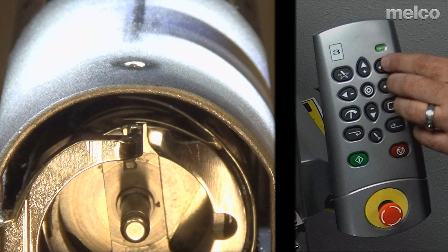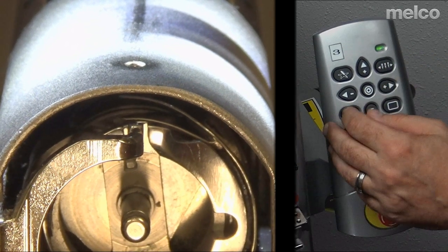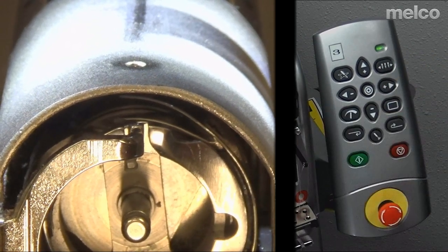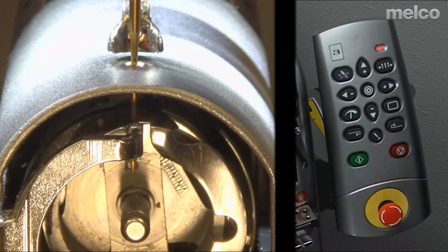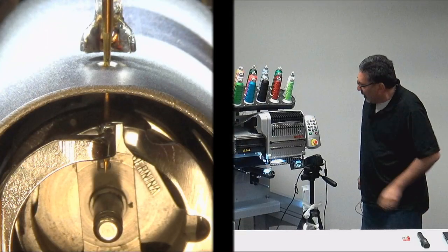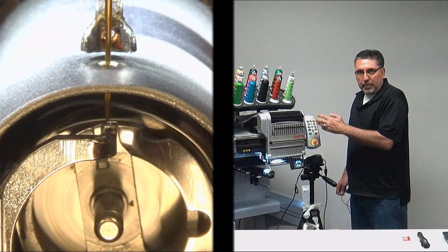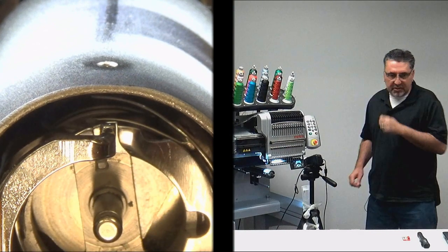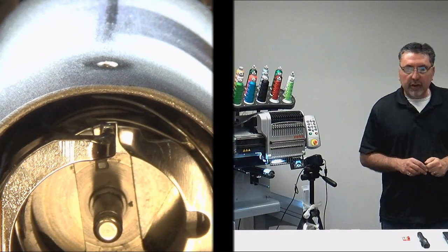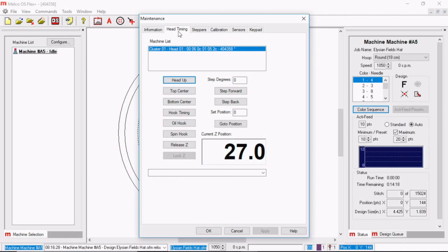And this should be needle 16, our last check. And 16 also looks good. So I'm going to do an adjustment up arrow. I'm going to leave the machine on needle 16, and I'm going to go to the operating software. In the operating software, I'm going to come over and I'm going to go to the calibration tab.